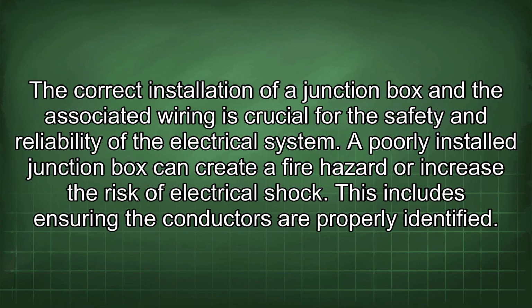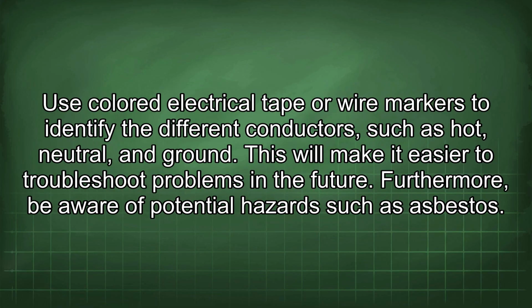The correct installation of a junction box and the associated wiring is crucial for the safety and reliability of the electrical system. A poorly installed junction box can create a fire hazard or increase the risk of electrical shock. This includes ensuring the conductors are properly identified. Use colored electrical tape or wire markers to identify the different conductors, such as hot, neutral, and ground. This will make it easier to troubleshoot problems in the future.